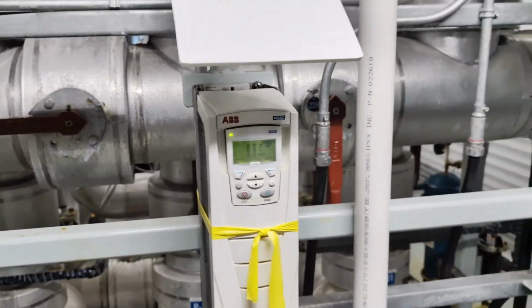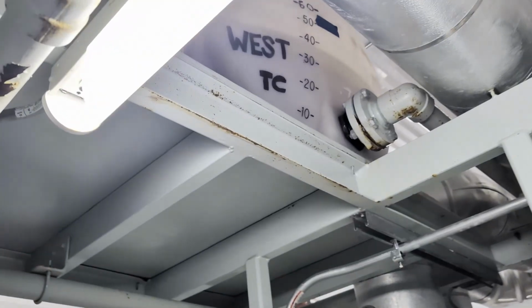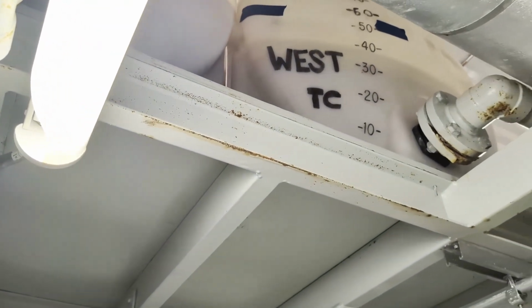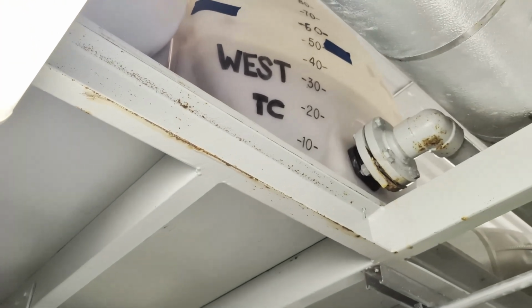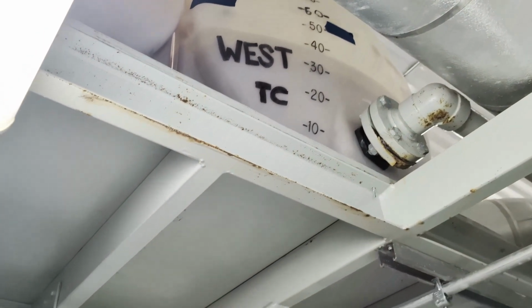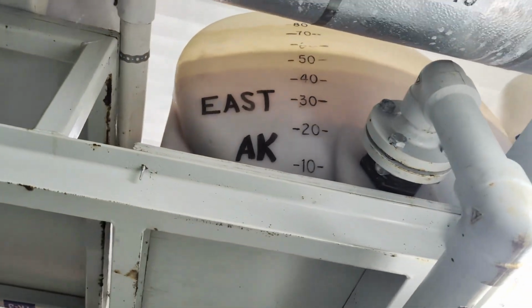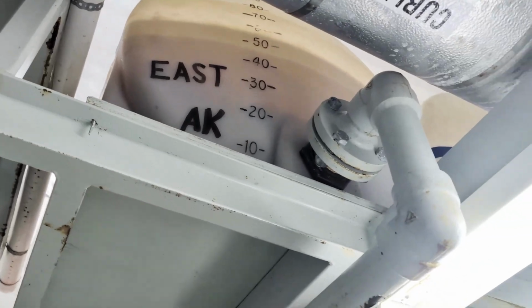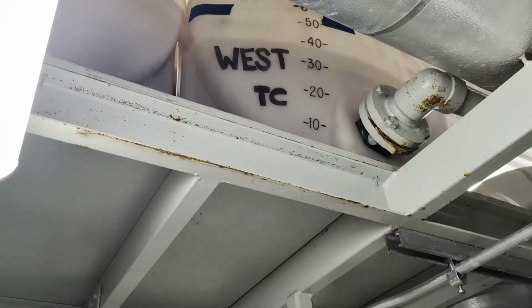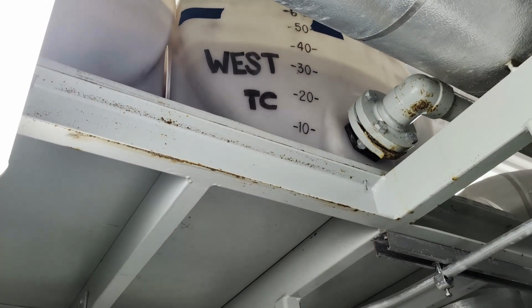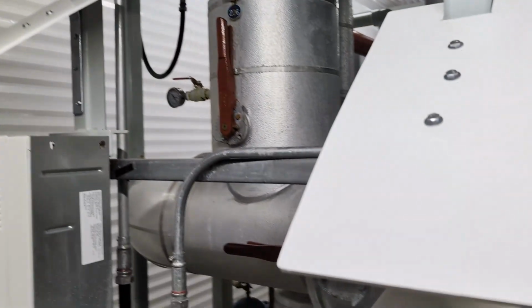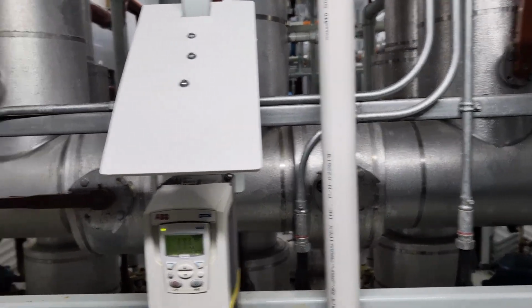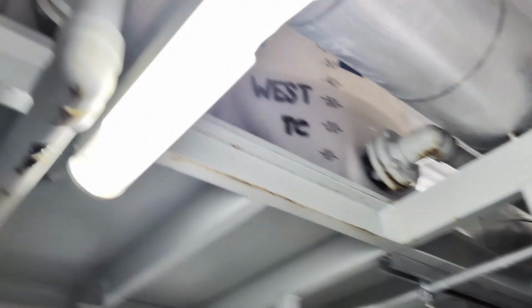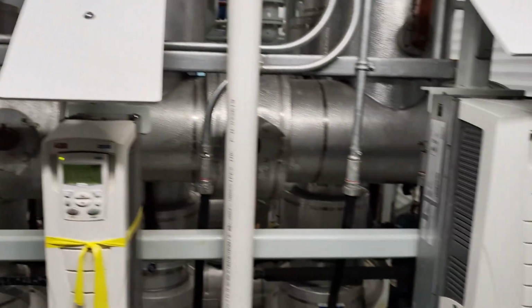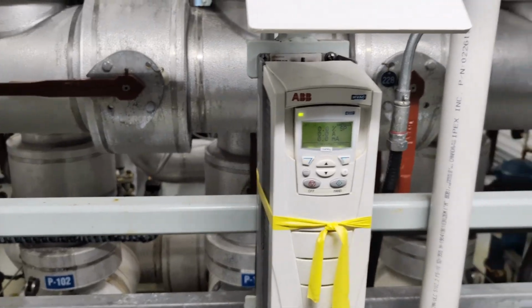So now we've got TC isolated. That also means now our brine tanks are going to be switched about. So now you can see that we actually are down at 40-ish on the TC brine tank, and we're at, let's call it 58 on the AK brine tank. Well, now this is AK and curling, whereas before curling was with TC. And based on that, I would say we probably lost about 10 gallons of brine since I opened up the valves outside going to the curling club. Now we'll see if the AK loses any brine, and then that'll tell us whether the issue is with the pipes to the curling club or if it's an issue in the TC floor.